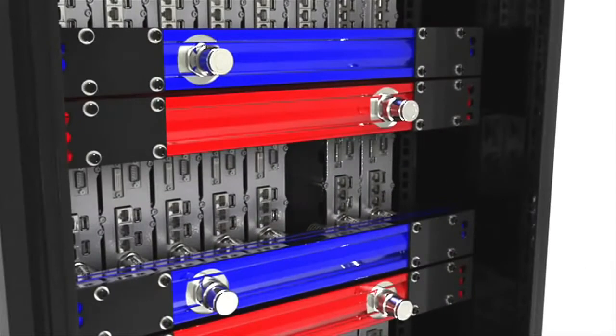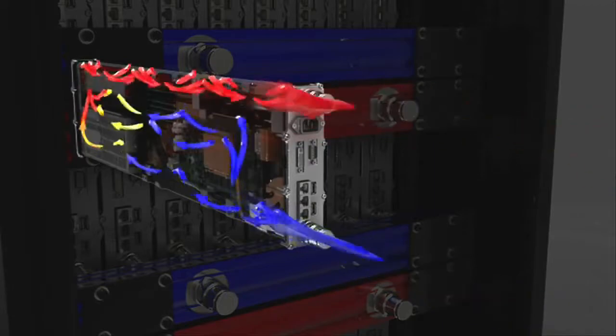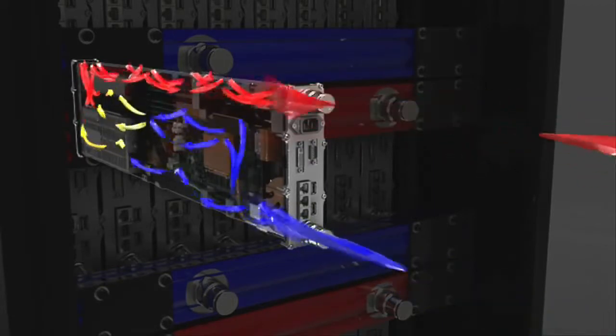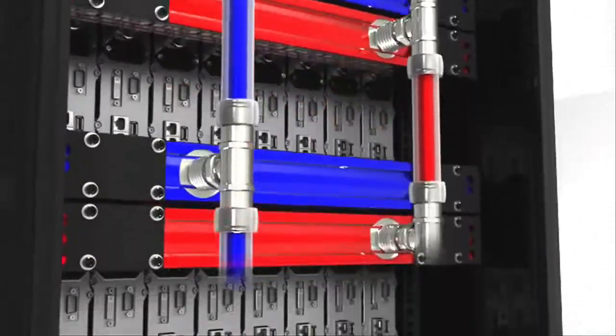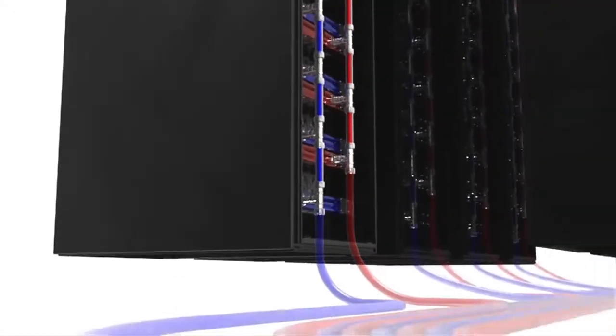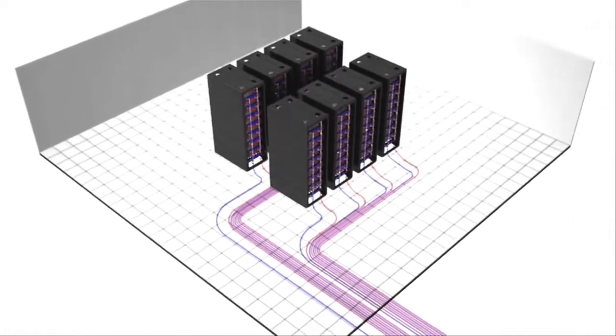LiquidCool systems mount directly into rack units connecting to the core coolant exchange system via dripless QuickConnect fittings. This exchange system pumps core coolant directly into each sealed chassis, fully submerging the server's internal components in dielectric liquid. The core coolant then flows out of the server chassis through the manifold system with an option for cooling inside or outside the data center.